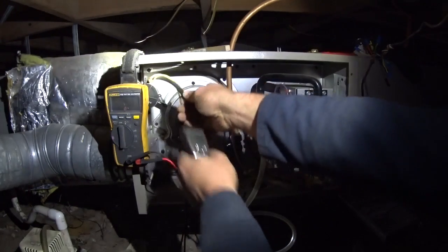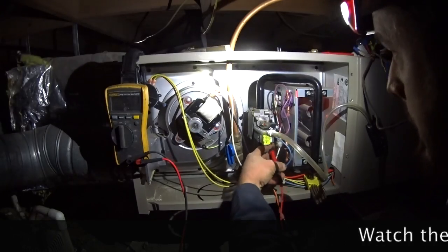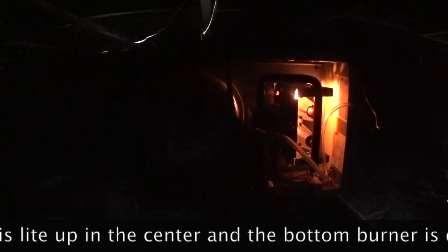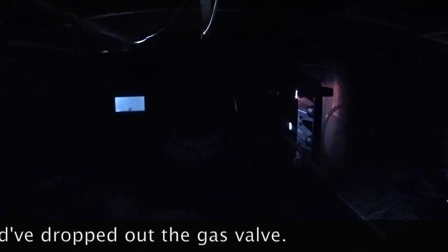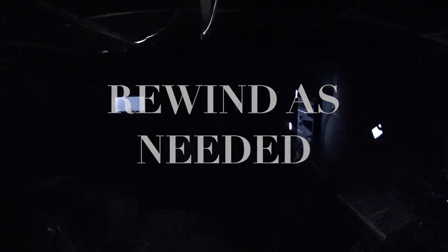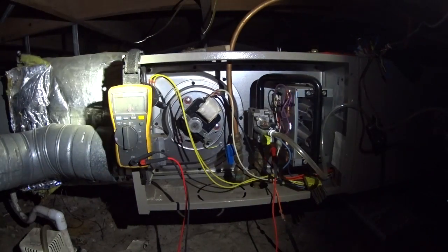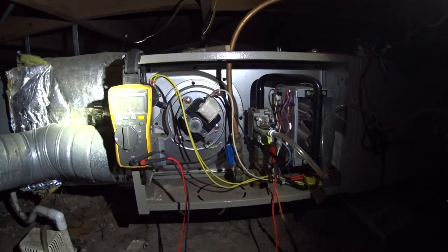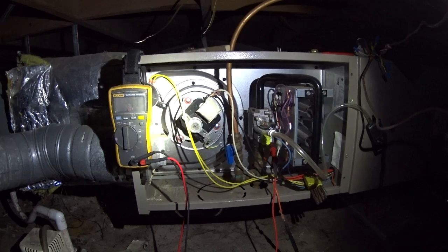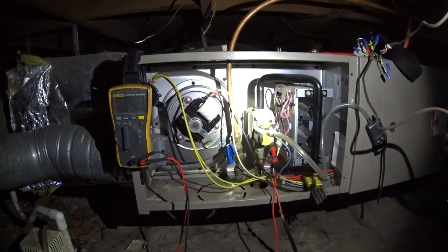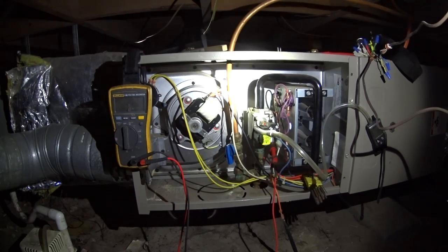Point four inches on the pressure switch. There's the igniter. Point three inches on the gas pressure. We are running LP. We got 4 milliamps on the flame sensor. This is actually the longest that the furnace has run, as far as what the customer said.